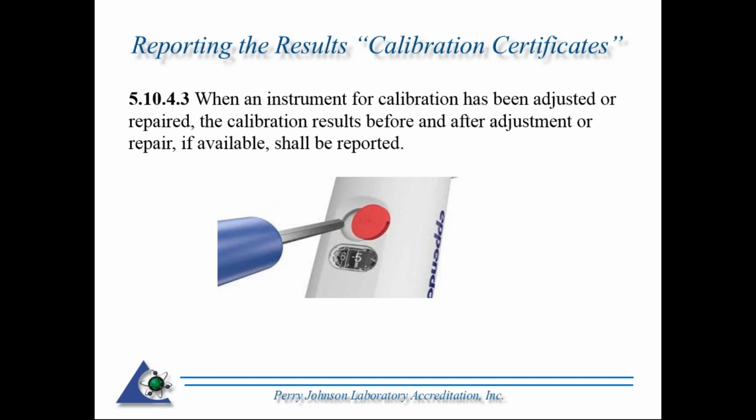That is "as left." So here what I tried to depict is a pipette. Typically a pipette, if you're getting an accredited report, would come in, it would be taken to the laboratory, and it would be tested in the conditions that it was received. So that's why I like to refer to them as used. Then if it failed or if it's going to be serviced, any adjustment, let's say the rings, seals, O-rings need to be replaced, needed to be relubed, and was adjusted to fall within tolerance. They would be the after adjustment values.